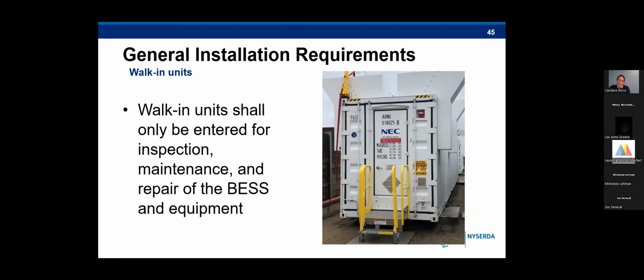And then our last general installation requirement here. These units are defined as an enclosure that is not for human occupancy, but can be entered for only maintenance, replacement, repairs, and inspections. For walk-in units, the risk of these containers presenting a life hazard inside during the event is significantly less than with systems located indoors, especially when compared to non-dedicated use buildings. Unless there really is a reason to believe someone is inside, you really should stay out. These containers are likely what you'll be seeing frequently throughout the state as storage becomes more prevalent. But once again, you really shouldn't be having your lunch in a walk-in container, and it should only be accessed for a real need of the system.